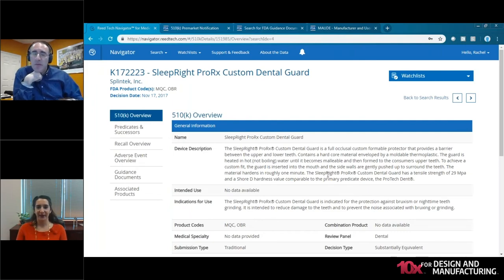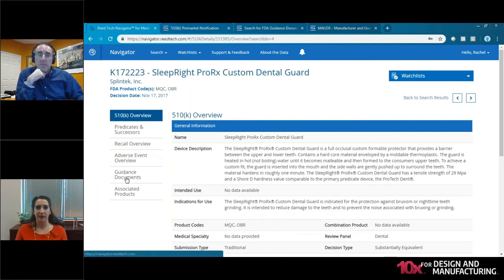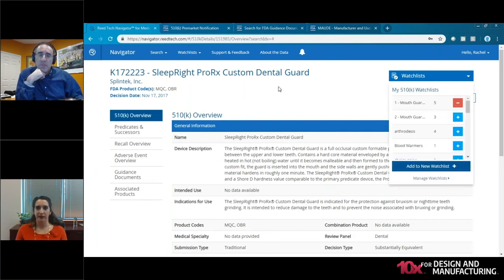Please continue. Okay, great. So some other things that can be important for predicate consideration is if there's been a lot of recalls, and depending on what those recall reasons are, same with adverse events, we have a little overview of that here. Also guidance documents, which I'll get into a little bit more in a minute. So for the watch list, like I said, you can add this 510K to as many watch lists as you like and put as many different 510Ks on each of those watch lists.